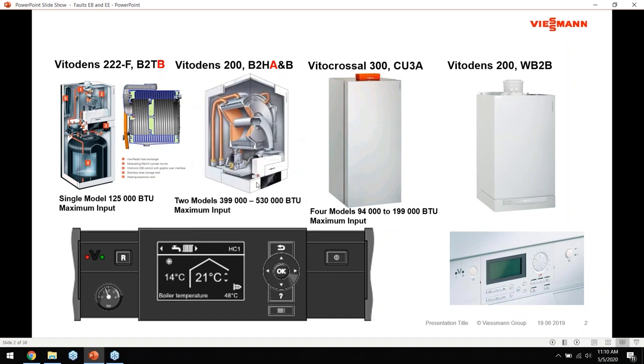The same applies to the B2HA 399 to 530. These boilers cross a line in terms of BTU input and fall under different code requirements - in some jurisdictions you may need another gas ticket to work on them. The heat exchanger has multiple supply returns to keep pump head requirements down. Unique features include flow sensors instead of flow switches, and a different gas valve with extra functions including a low gas pressure switch and a valve proving pressure switch.